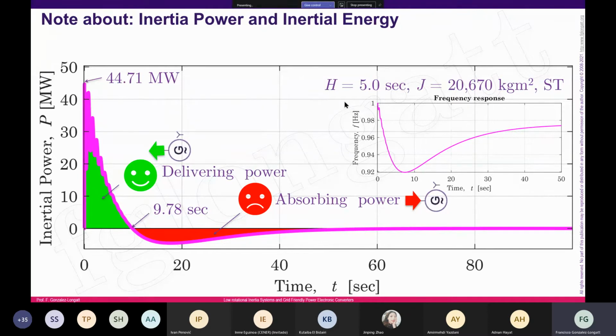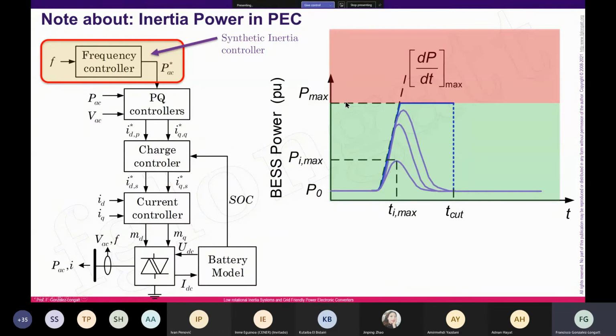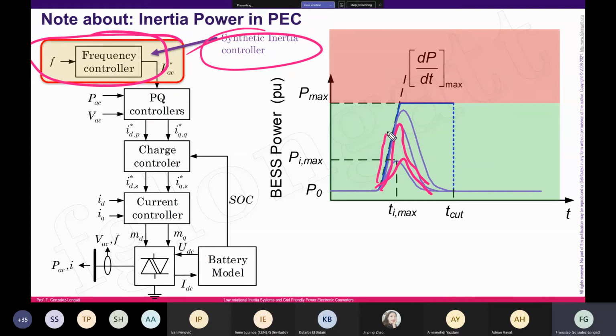Another thing that I tell you is that we are doing things in a very different way, because in the case of a synchronous machine, you have the possibility of overload. But if you look over here, I am using a battery energy storage system, and this battery energy storage system is enabled with an inertial response. And what is the situation? Well, depending on the frequency deviation and the inertia constant, you will have different contributions. But that contribution has a limit, because if you reach the maximum power of the power converter, you are saturating the converter, reaching the maximum current and the maximum power that it can deliver. As a consequence, this converter will never be identical to the inertial response that is provided by a classical synchronous machine, okay?